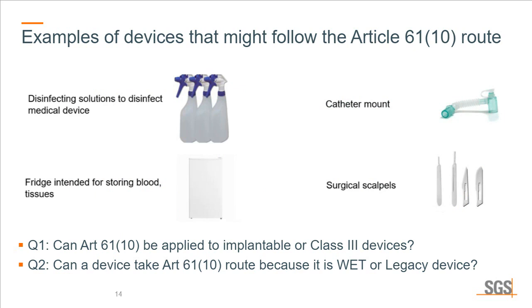The other question is, can a device take this route because it is a well-established technology or legacy device? And the answer is that it may or may not, but it does not depend on whether it's a well-established technology or a legacy device. It is more about those factors that I mentioned before, about patient contact and the risk of the device. So just because they are well-established technology or legacy devices, it doesn't automatically mean that they can follow this route. We have to look at the nature of the device, patient contact, and the risk class of the device.